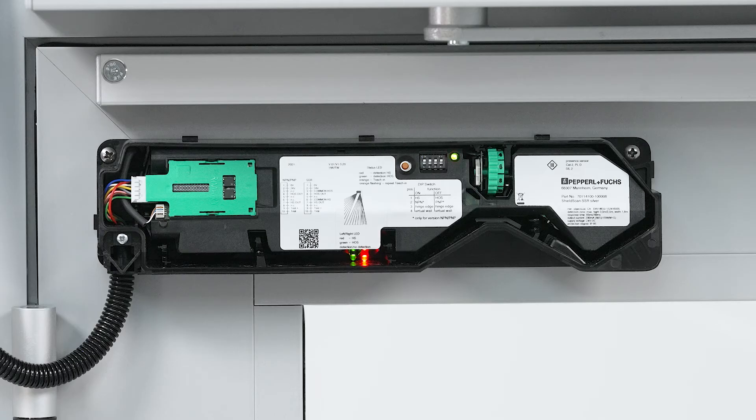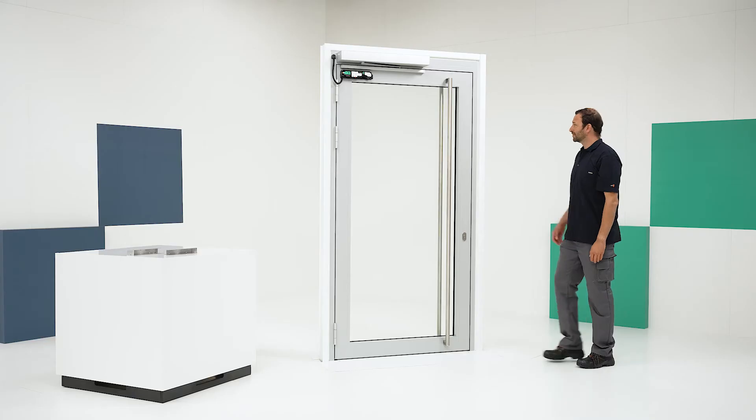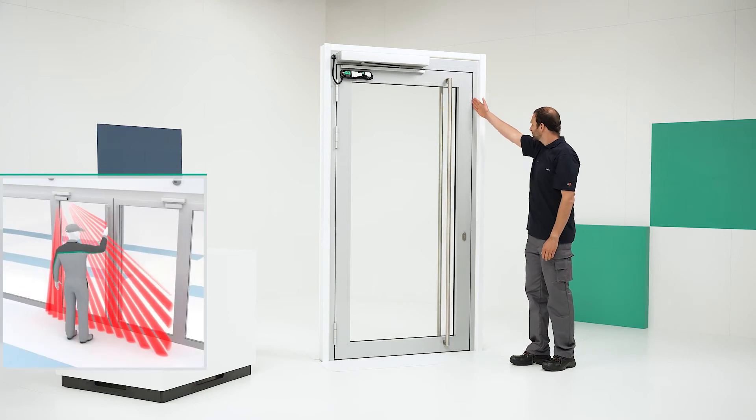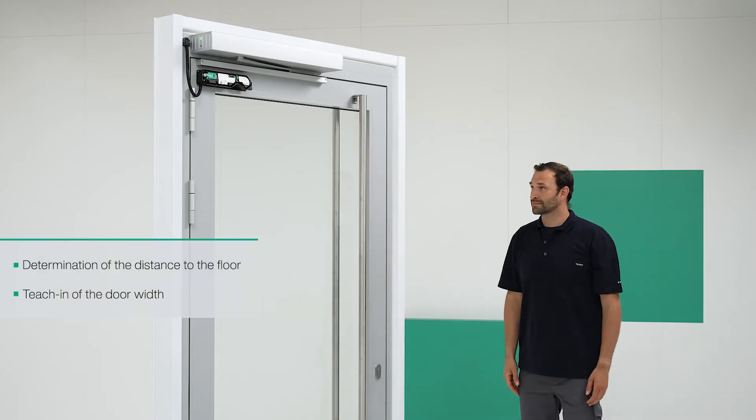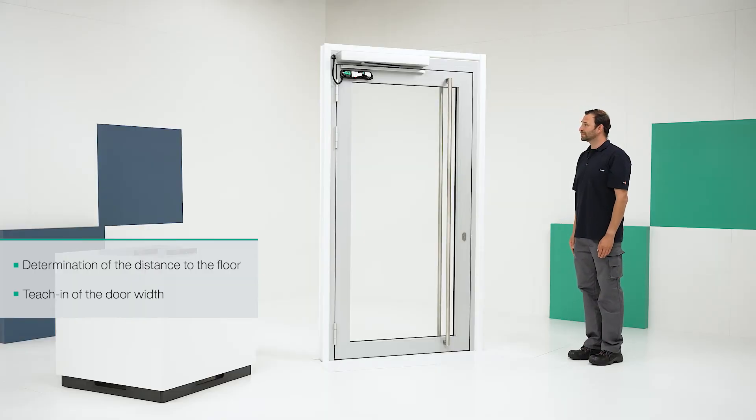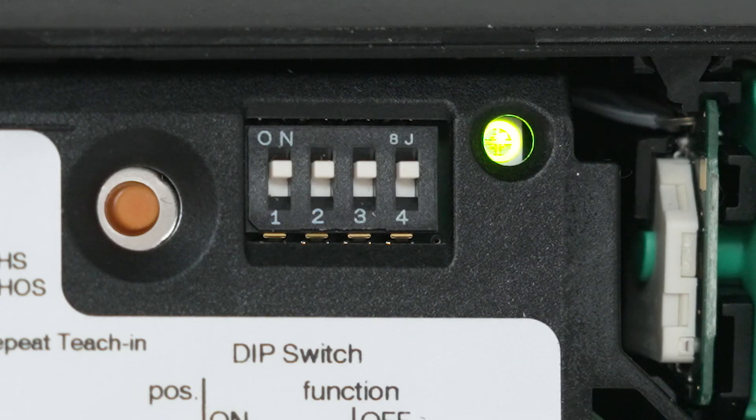When the status LED starts flashing green, perform gesture control within 10 seconds. Gesture control means interrupting the beams with your arm, covering a section of at least 60 cm along the leading edge. Once the gestures have been detected, the status LED will flash red for 2 seconds. As soon as the status LED flashes green again, the output is enabled.